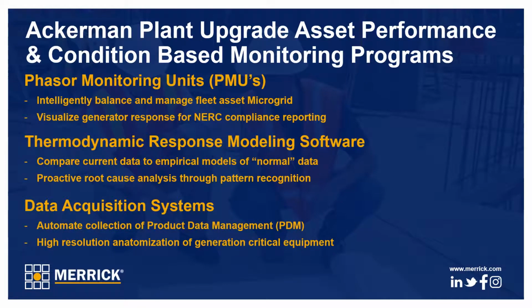One of the major highlights from this project, especially from an owner's and operations standpoint, is that it supports the ongoing asset performance and condition-based monitoring programs. Capturing of the generator's synchrophasor data with the use of the relay PMU functions provides input in the fleet system model and is utilized to balance and manage in a microgrid fashion.